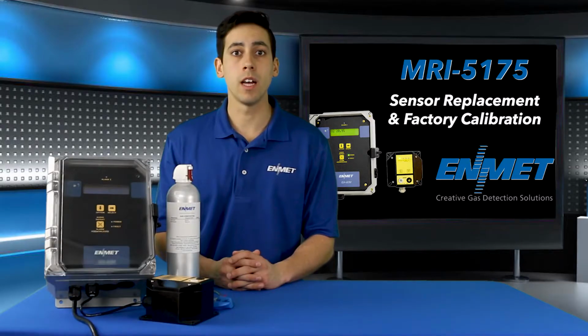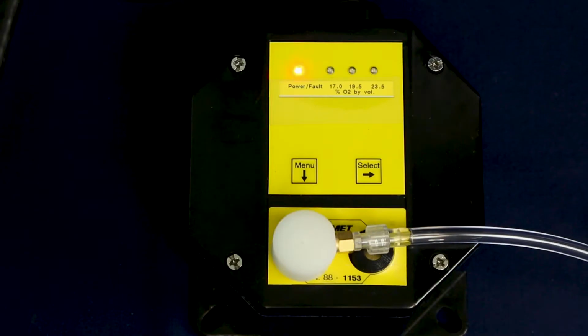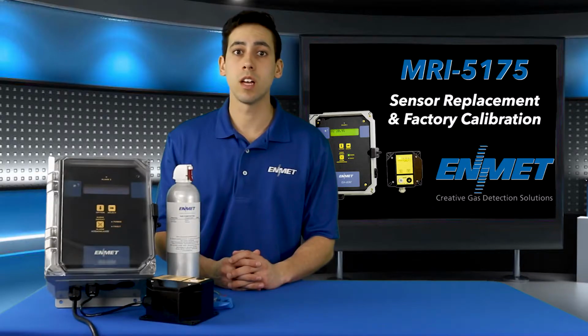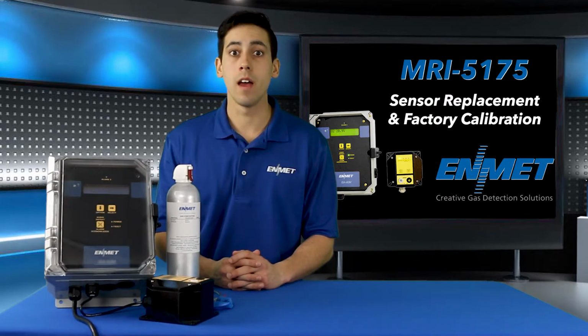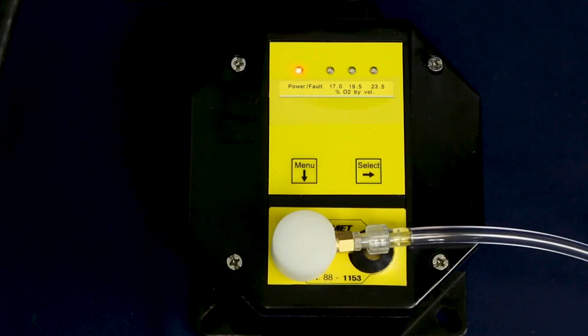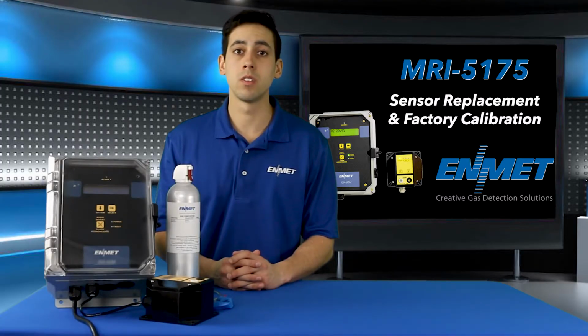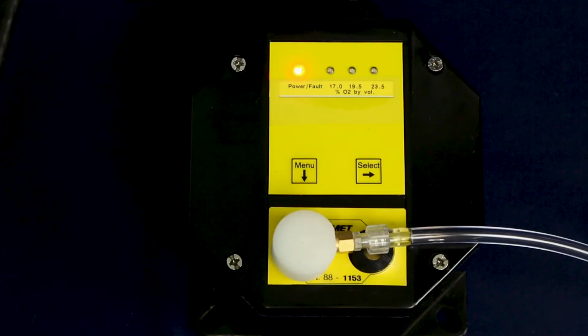Observe the power fault LED, and when the signal has stabilized, the power fault LED will show green for 3 seconds, indicating a successful calibration, and then flash red, red, red on repeat. If the calibration was unsuccessful following the 60 to 120 second stabilization time, the power fault LED will show red for 3 seconds and then flash red, red, red on repeat.